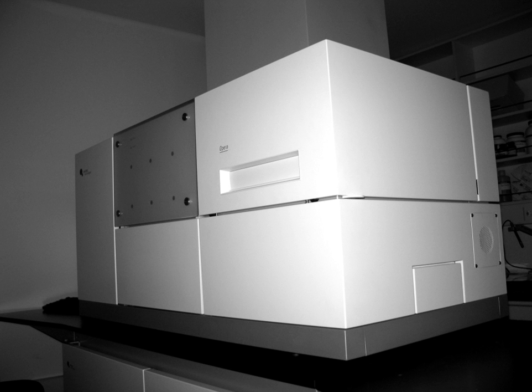Using automated microscopes means that some images might be out of focus. Automated focus finding systems may sometimes be incorrect, contain a small number of cells, or be filled with debris. Therefore, the images generated will be harder to analyze than images acquired by an operator, as they would have chosen other locations to image and focus correctly.